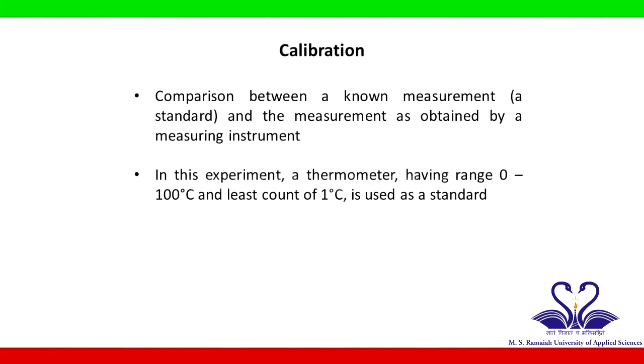Calibration is necessary for verifying the correctness of a reading as obtained by a measuring instrument. It is the comparison between a known measurement, which is a standard, and the measurement as obtained by a measuring instrument. It is carried out for a new instrument, a repaired or a modified instrument, after the lapse of a specific time period, after a specific number of hours of usage of an instrument, and in other similar scenarios. In this experiment, a thermometer having a range of 0 to 100 degrees centigrade and least count of 1 degree centigrade is used as a standard.